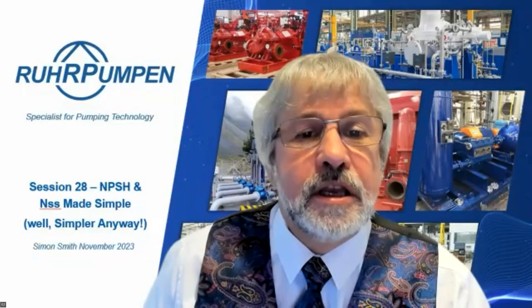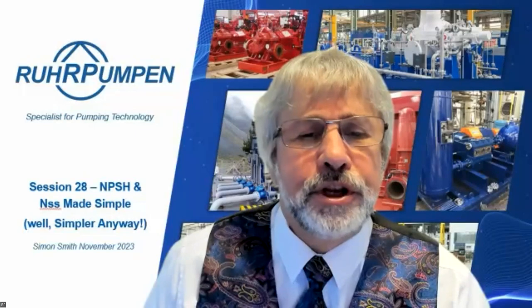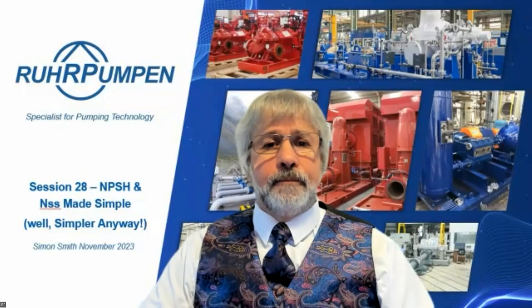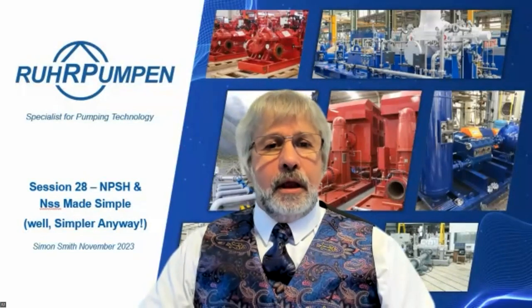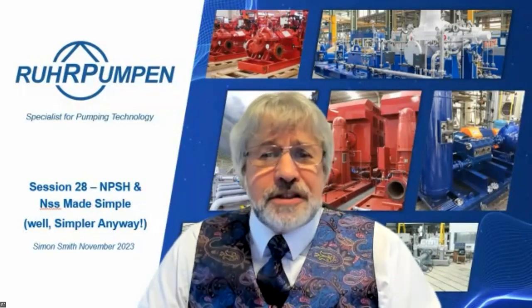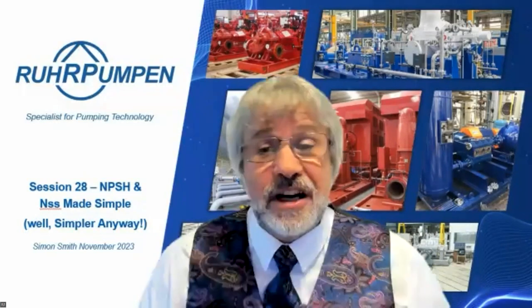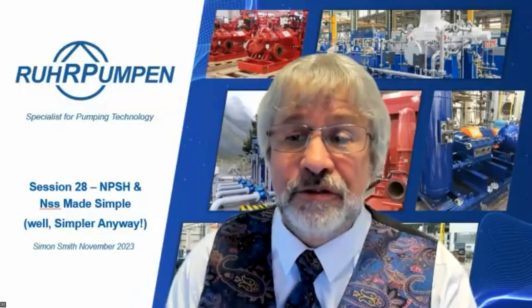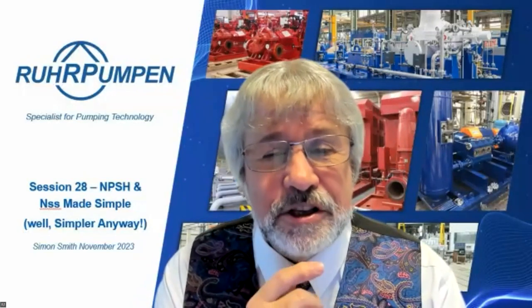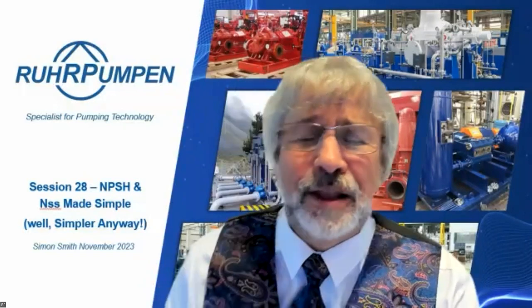A question from Nimesh Shah via Dharmesh Kumar Panchal: please advise points to be taken care of from an NPSH point of view for parallel and series operation. For parallel operation, you simply need to make sure the NPSH available exceeds the NPSHr by a safety margin. For series operation, only the first pump potentially has an NPSH problem - the second pump will have plenty of NPSH.